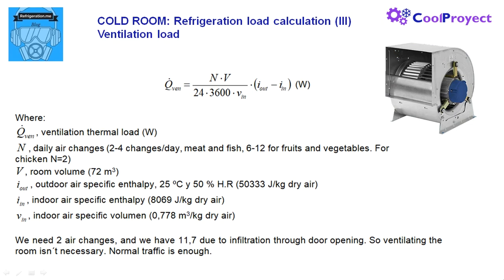The ventilation load is for some products which need air changes to remove respiration and metabolic vapors or fumes. For example, meat and fish need about 2 to 4 air changes per day. Fruits and vegetables need more, about 6 to 12. And some products like onion or garlic require more than 20 changes per day usually. It is because these products generate a lot of sulfur vapors we have to remove to keep the cold room atmosphere clean.